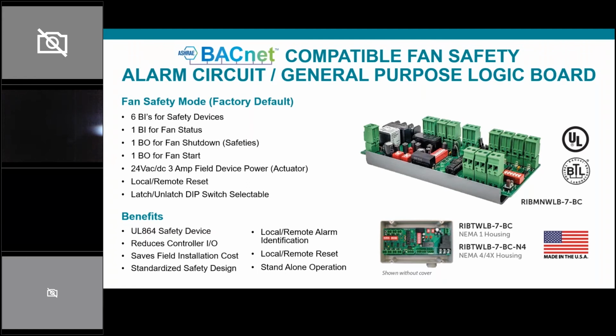And now, unlike the MNLB-6 model that we have, this board has a second relay on board, which by default is bound to the 7th binary input. Now, this input is for fan status, and if closed, will energize binary output 2 to start the fan back up. Now, a property of binary output 2 allows for its binding with binary input 7 to be disabled, and when this happens, it disables a safety function, and the board can then function like a standard BACnet RIB with 7 binary inputs and 2 binary outputs.